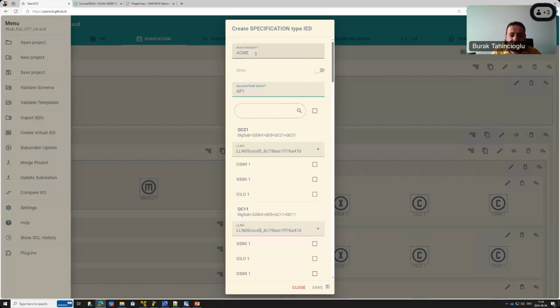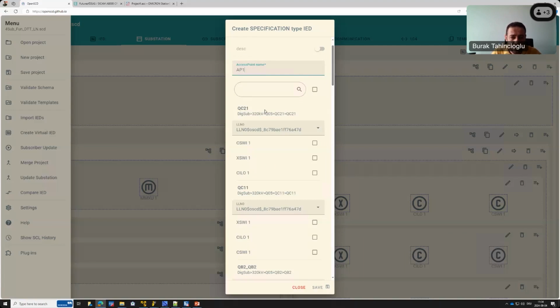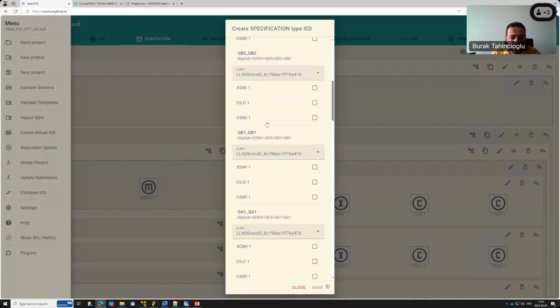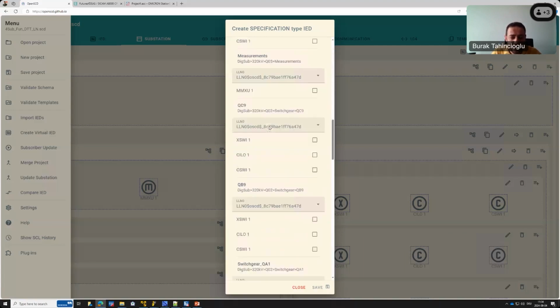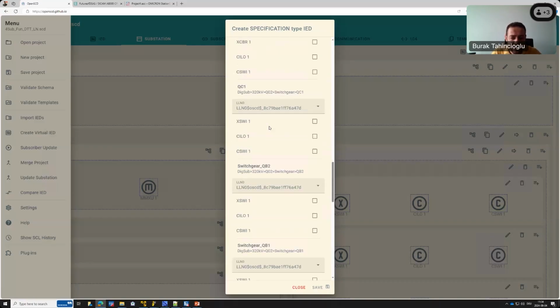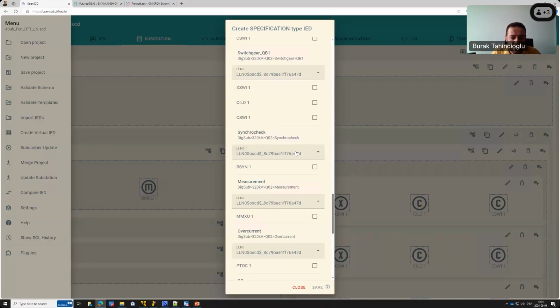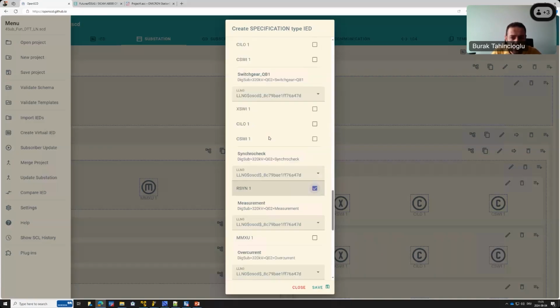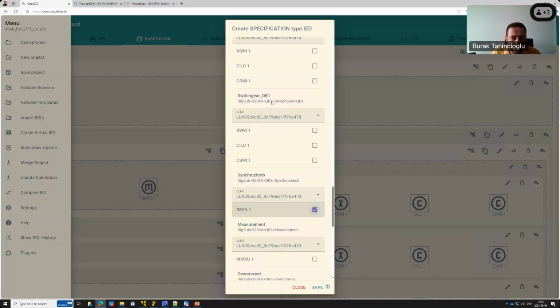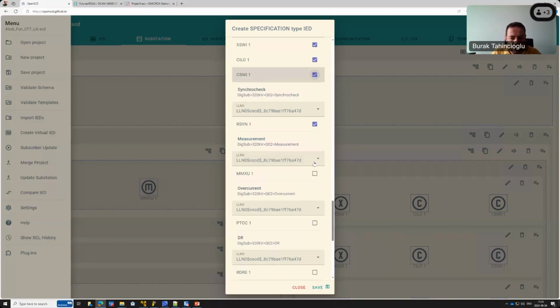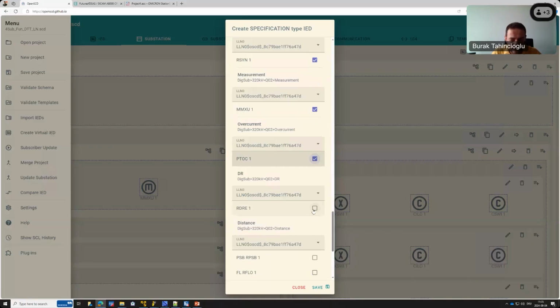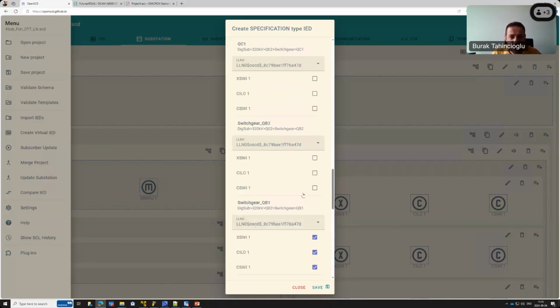So which IED are we creating now? Maybe we are creating the line bay protection control. That would mean we need to assign the logical nodes of the line bay. You remember the line bay - we would need a synchro check, so we would definitely need this RSYN, once I click all the RSYN logical nodes. Okay, I will not click all, just to save some seconds.